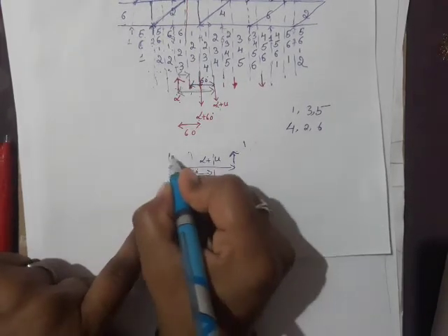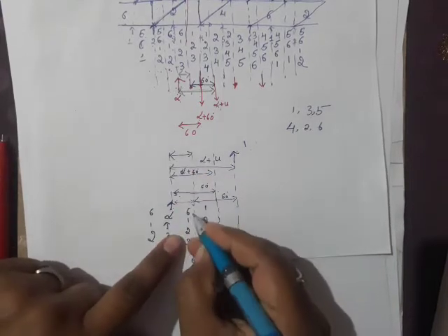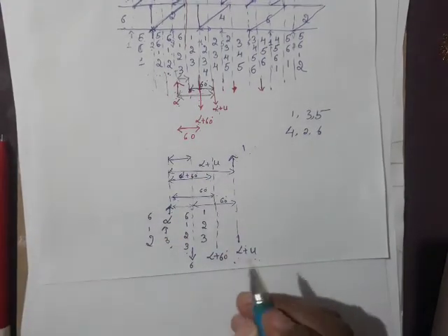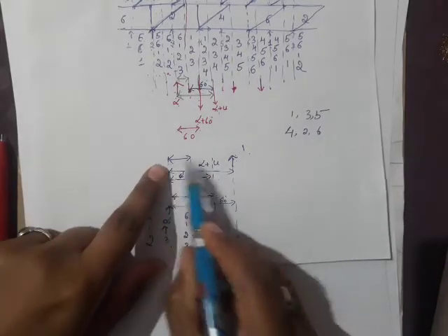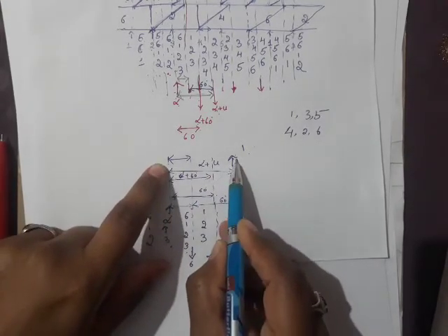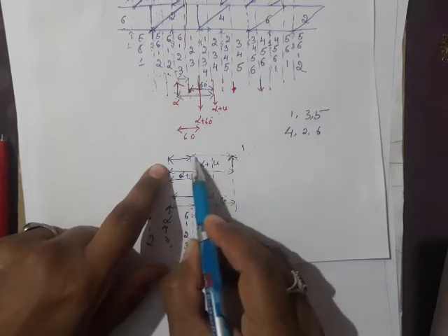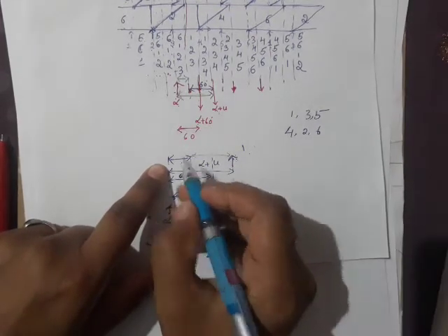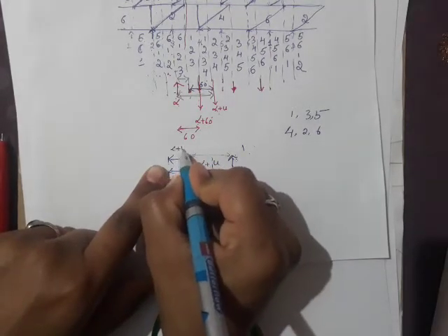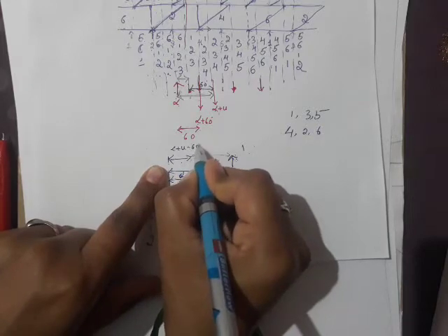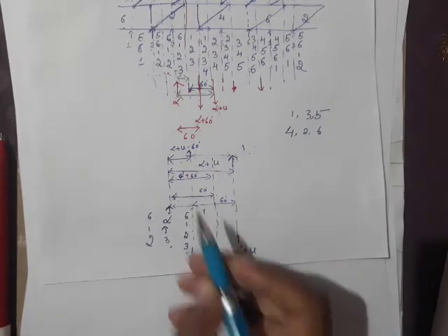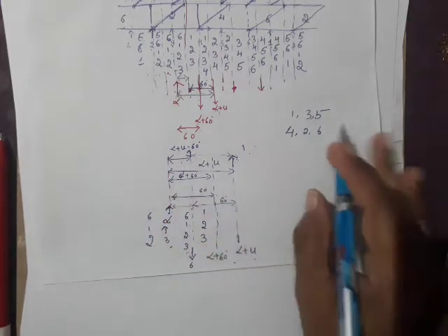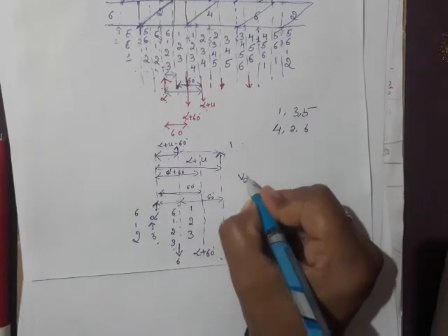Then what about this period? Here we have 4 valve conduction. So we need to know what is that period, total duration. Totally we know from here to here it is alpha plus u, and from here to here it is 60 degree. So what is this duration? Alpha plus u minus 60 degree. At this point it is alpha plus u minus 60 degree. Means 4 valves will conduct from alpha to alpha plus u minus 60 degree. I can write the voltage here.